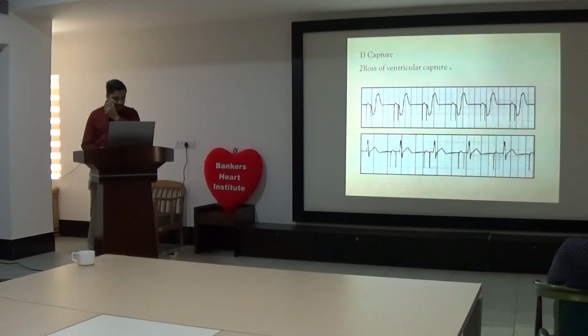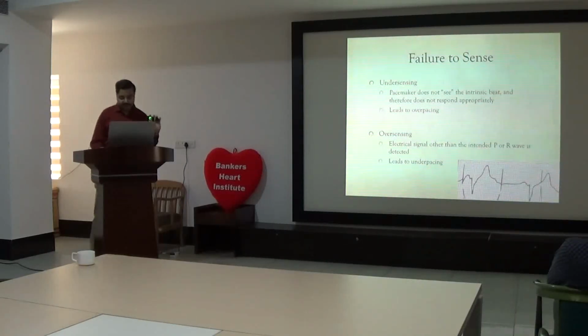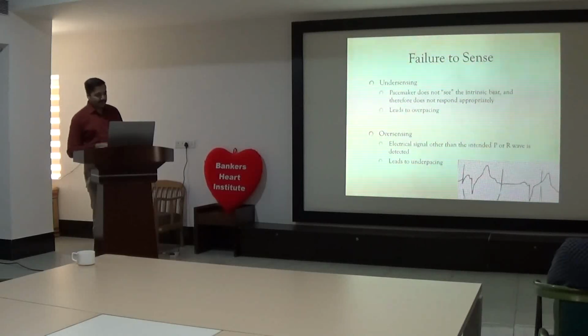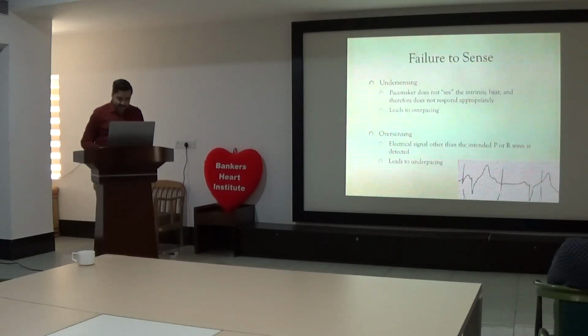Then we come to sensing. Now there are two problems: one is undersensing, one is oversensing. What is undersensing? In undersensing, the pacemaker does not see the intrinsic beat and therefore does not respond appropriately. Like if you set the sense mode at 0.5 millivolt, if the pacemaker goes into undersensing mode, it won't sense anything and it will continue pacing everything because it is not sensing. So undersensing will lead to overpacing.